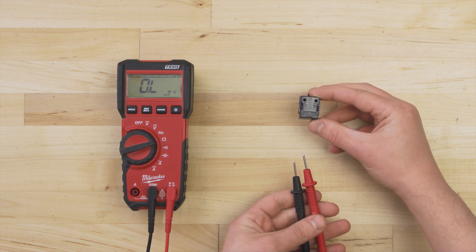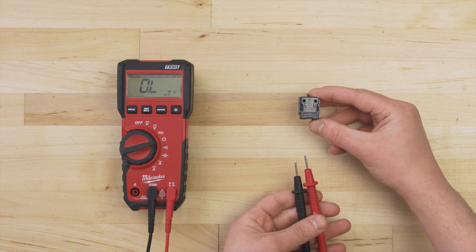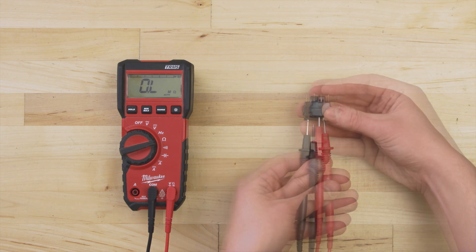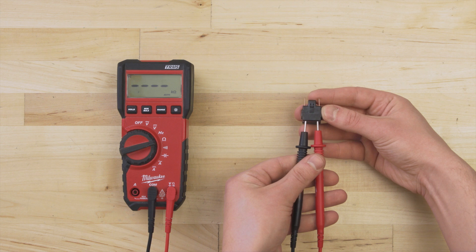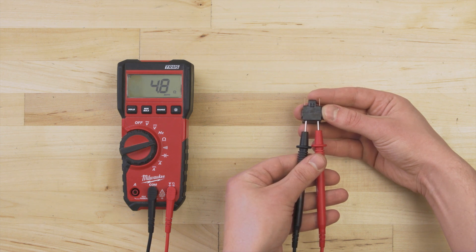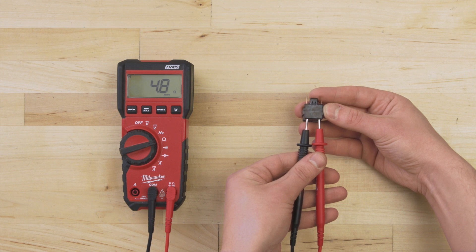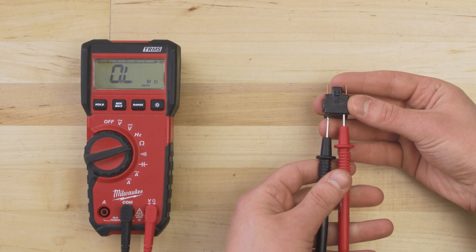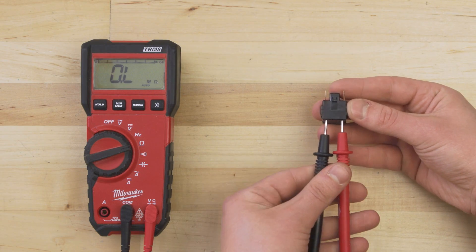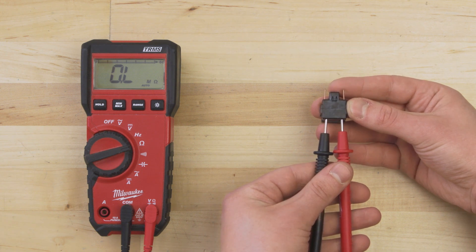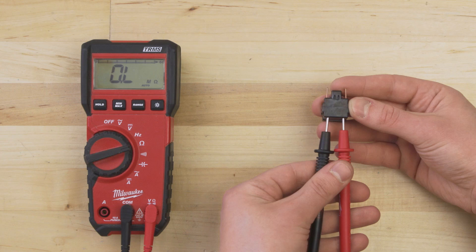You can test the PTC relay for resistance. Simply test between the R and S terminals, which might be labeled 5 and 6. The resistance should be between 3 to 12 ohms at room temperature. If there is no resistance and no continuity, or if the resistance is extremely high, then the relay has failed and will need to be replaced.